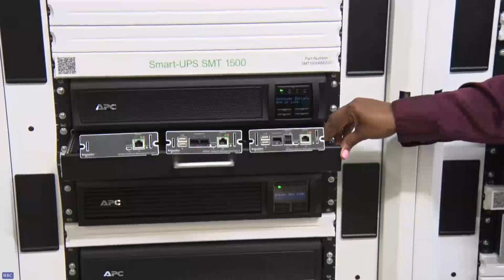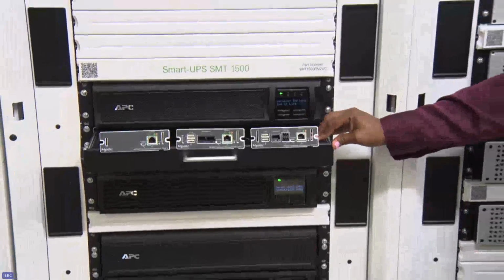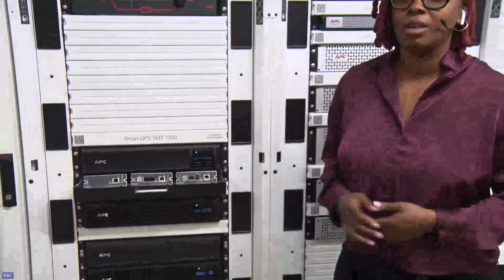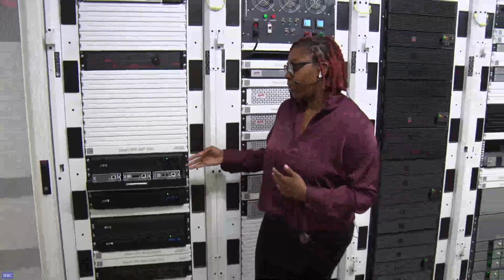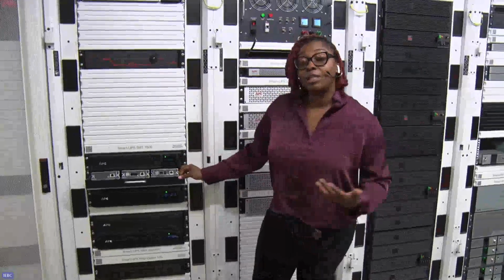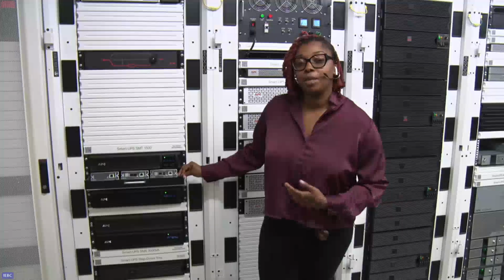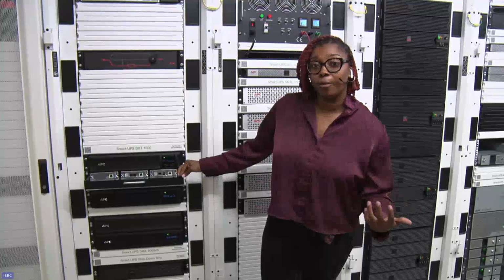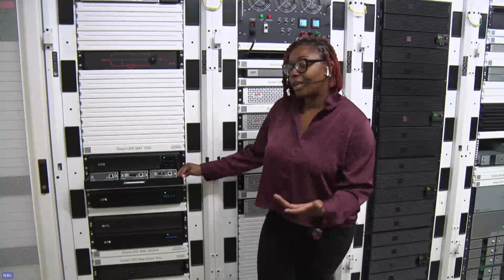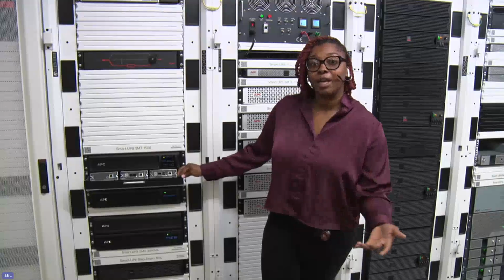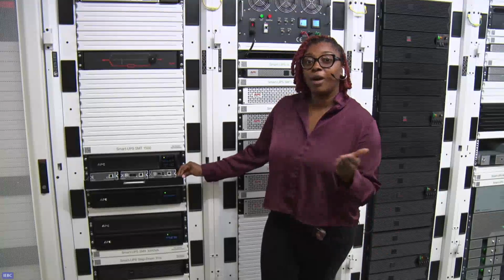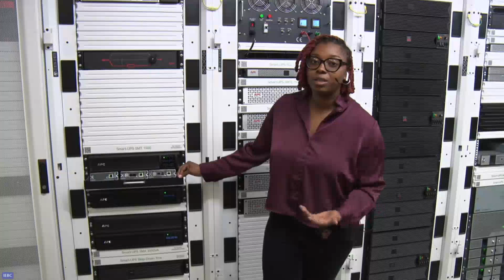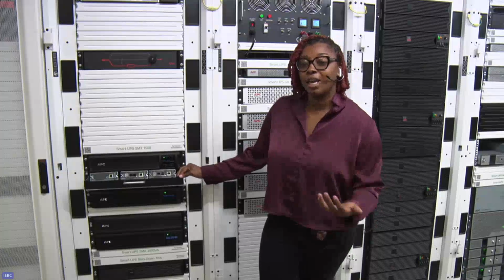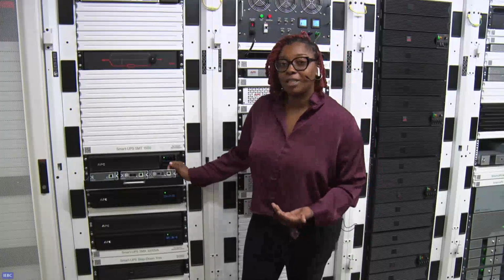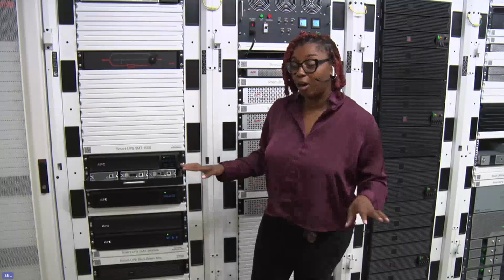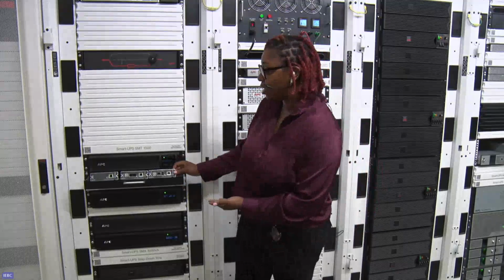With manageability, you can toggle outlet switches on and off, which is important because you can set up notifications so the UPS system lets you know whether it's operating on battery or utility power. If something happens and it goes to battery, you get that notification, and you can toggle outlets on and off to safely shut down equipment or save critical information before a full, complete shutoff. That's where manageability comes into play.